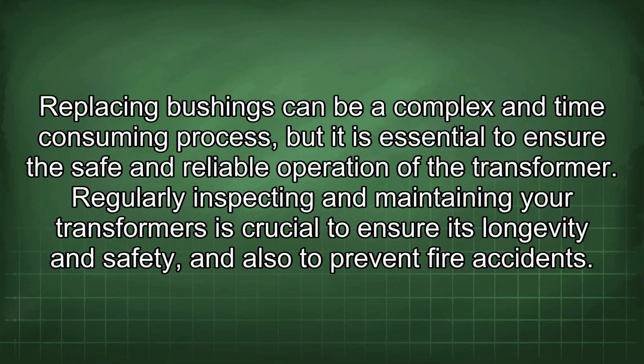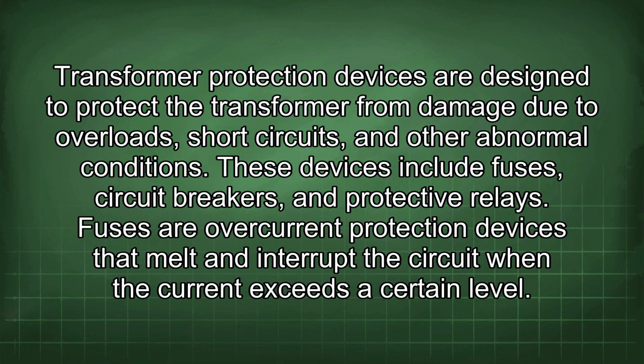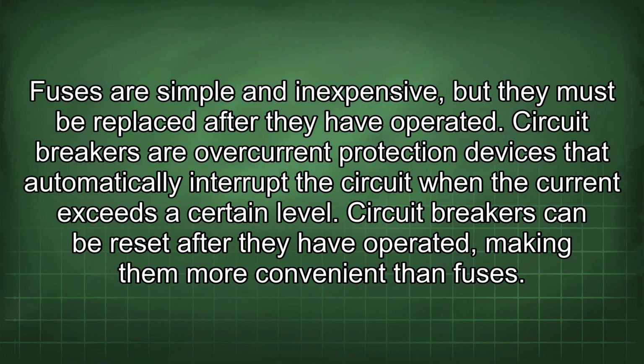prevent fire accidents. Transformer protection devices are designed to protect the transformer from damage due to overloads, short circuits, and other abnormal conditions. These devices include fuses, circuit breakers, and protective relays. Fuses are overcurrent protection devices that melt and interrupt the circuit when the current exceeds a certain level. Fuses are simple and inexpensive, but they must be replaced after they have operated. Circuit breakers are overcurrent protection devices that automatically interrupt the circuit when the current exceeds a certain level. Circuit breakers can be reset after they have operated, making them more convenient than fuses.